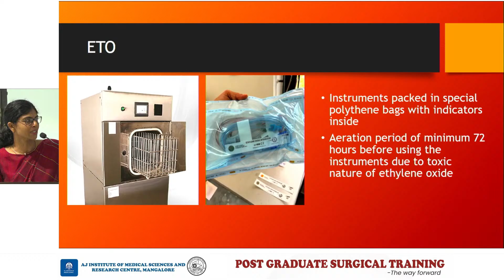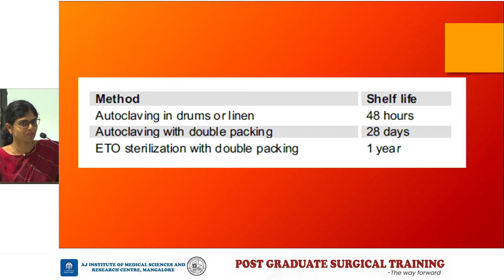So the thing to remember here is that autoclaving in drums or linen, the shelf life is just 48 hours. Whereas if you autoclave with double packing, like in a B-class autoclave, then you can keep it for around 28 days. And ETO sterilization with a double packing usually can be kept for a year.